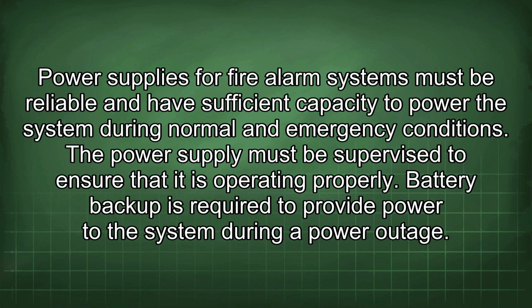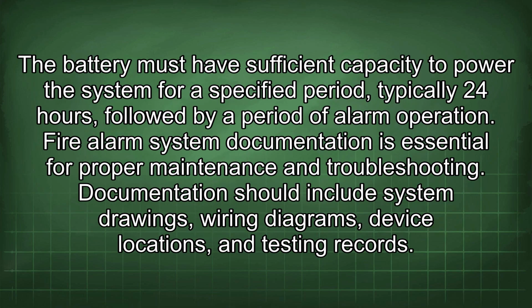Power supplies for fire alarm systems must be reliable and have sufficient capacity to power the system during normal and emergency conditions. The power supply must be supervised to ensure that it is operating properly. Battery backup is required to provide power to the system during a power outage. The battery must have sufficient capacity to power the system for a specified period, typically 24 hours, followed by a period of alarm operation.